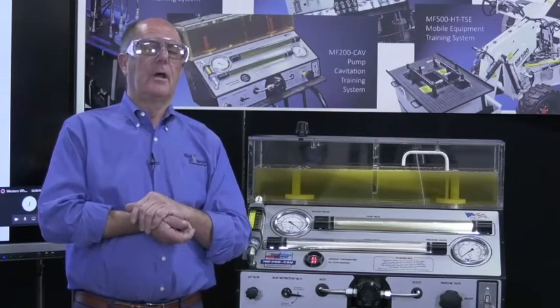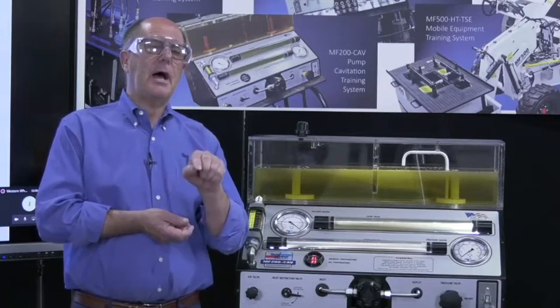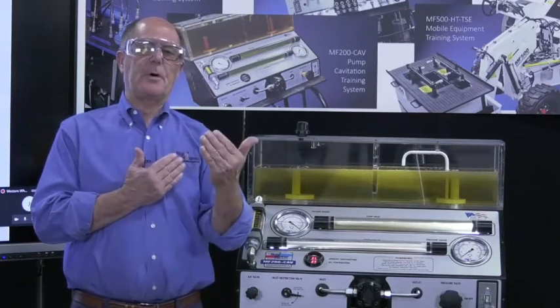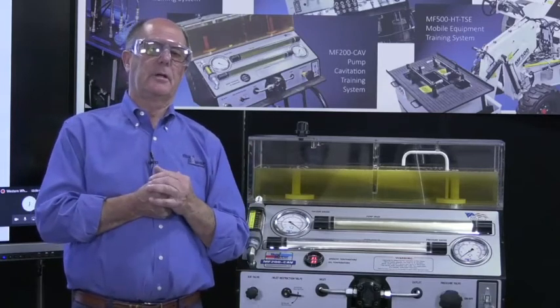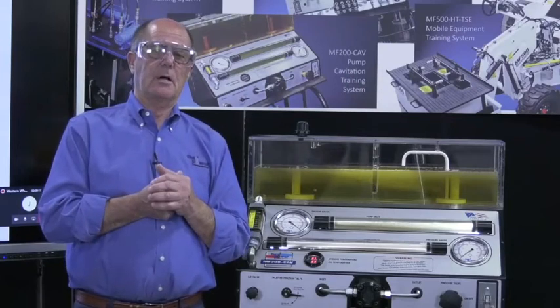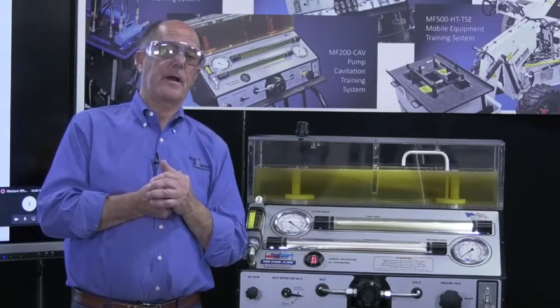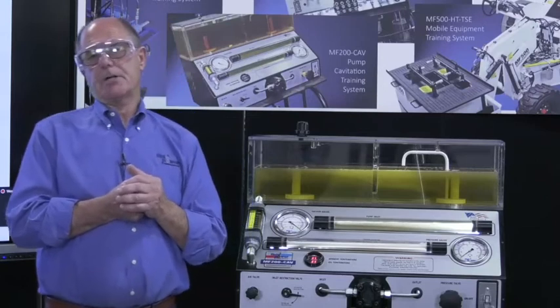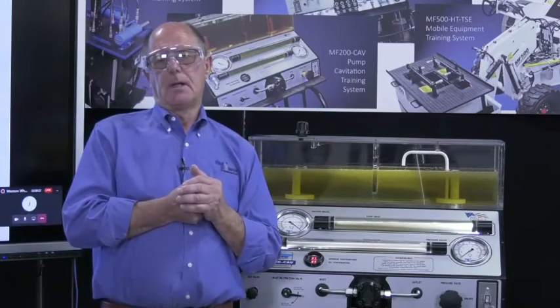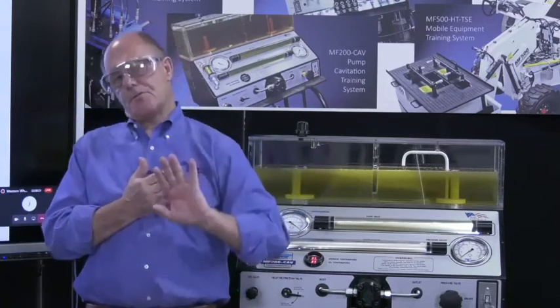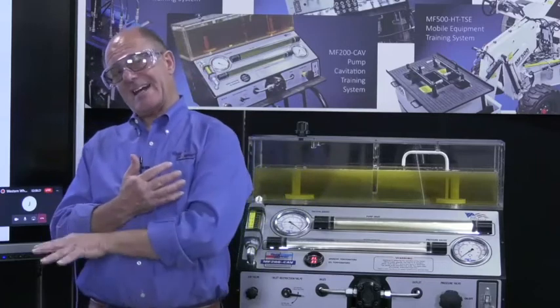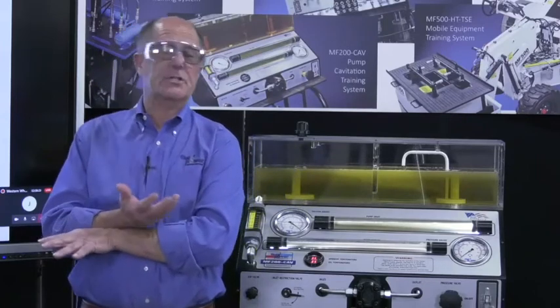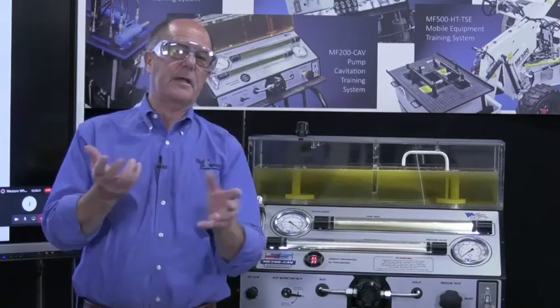Second challenge. Has the designer made it possible for me to put the pump onto full stroke to make this observation? In other words, I can't be in the engine compartment while the operator is operating a front-end loader, and I'm running a pressure compensated pump or a load sensing pump. Shouldn't I be able to bring the pump onto full flow, because then I can actually see what the worst case scenario is? In other words, be careful of this.